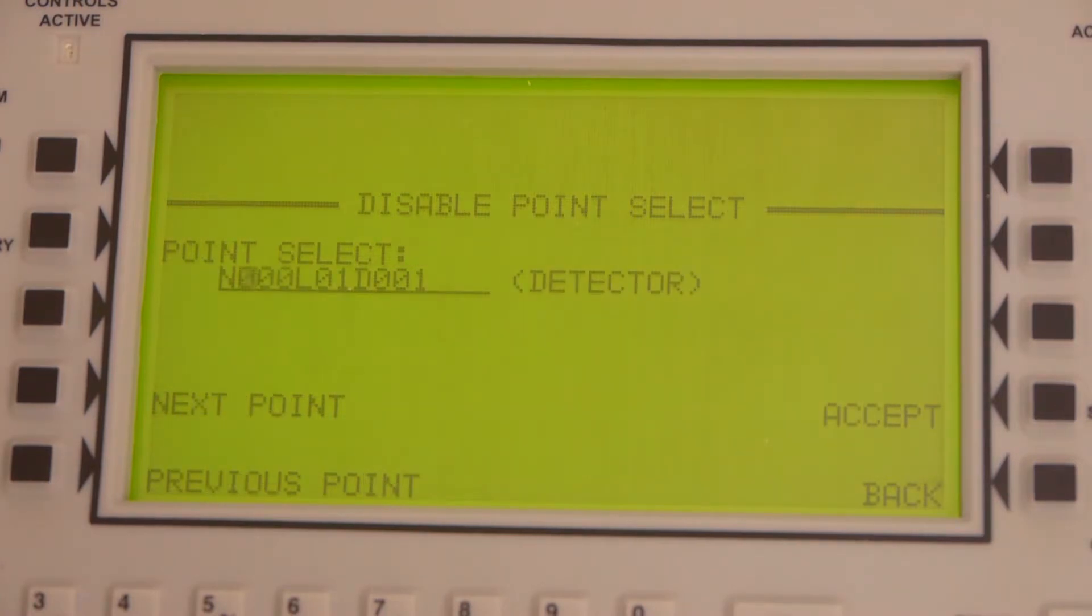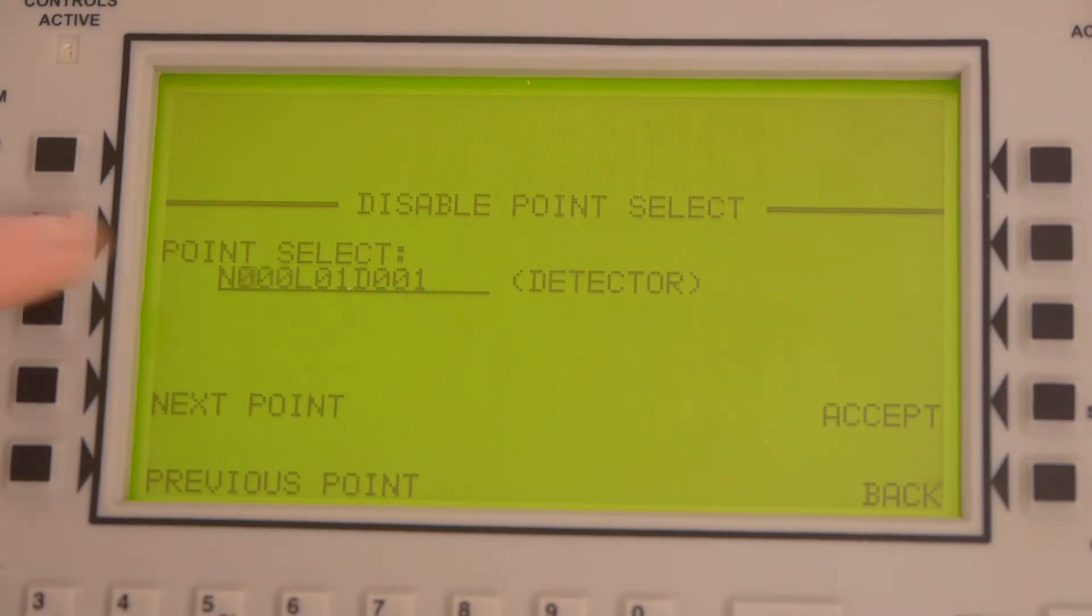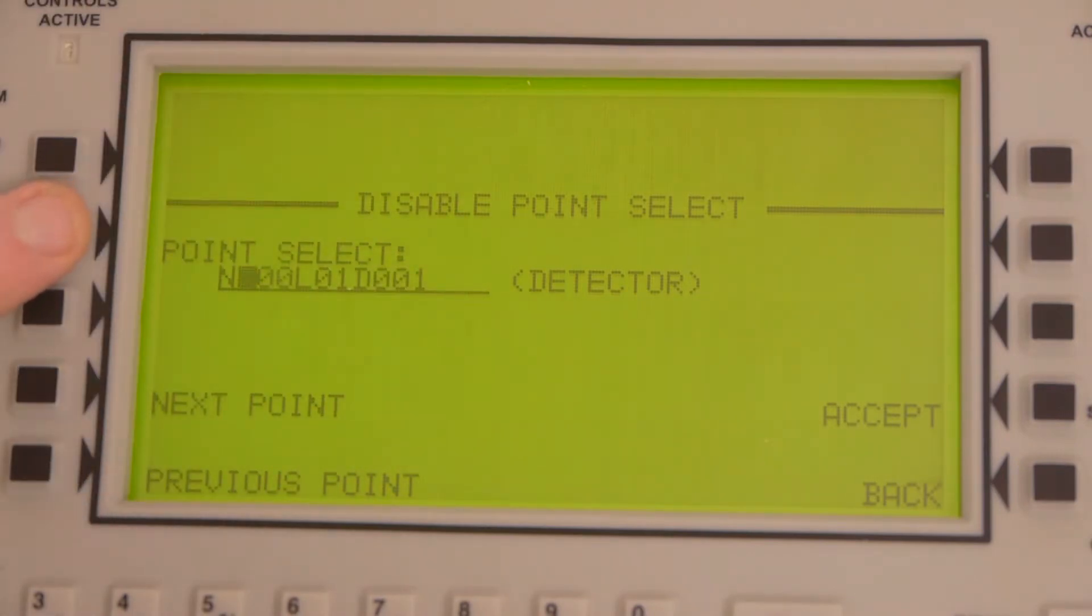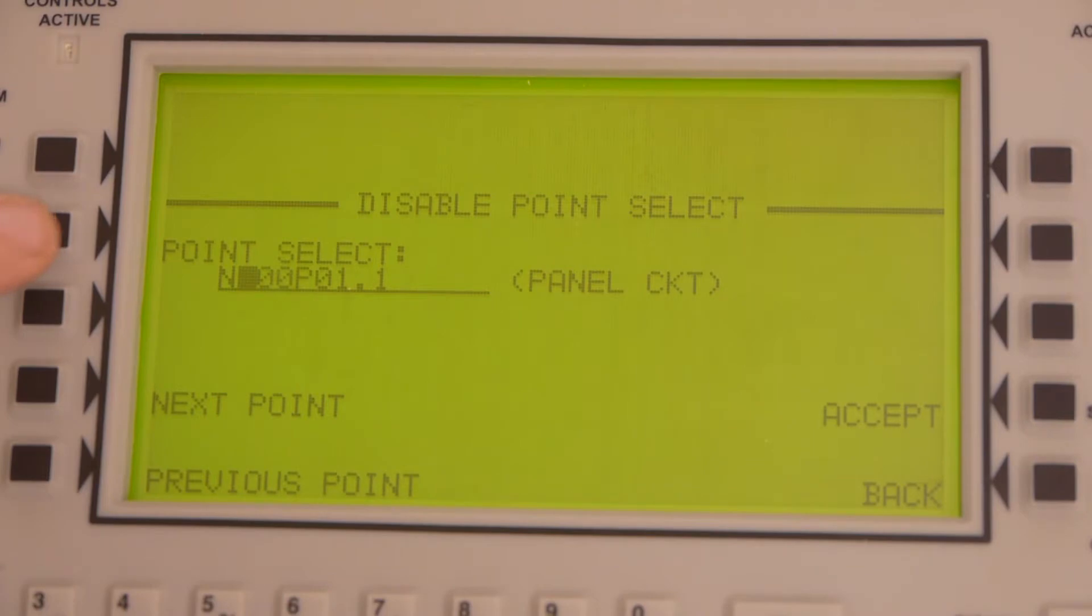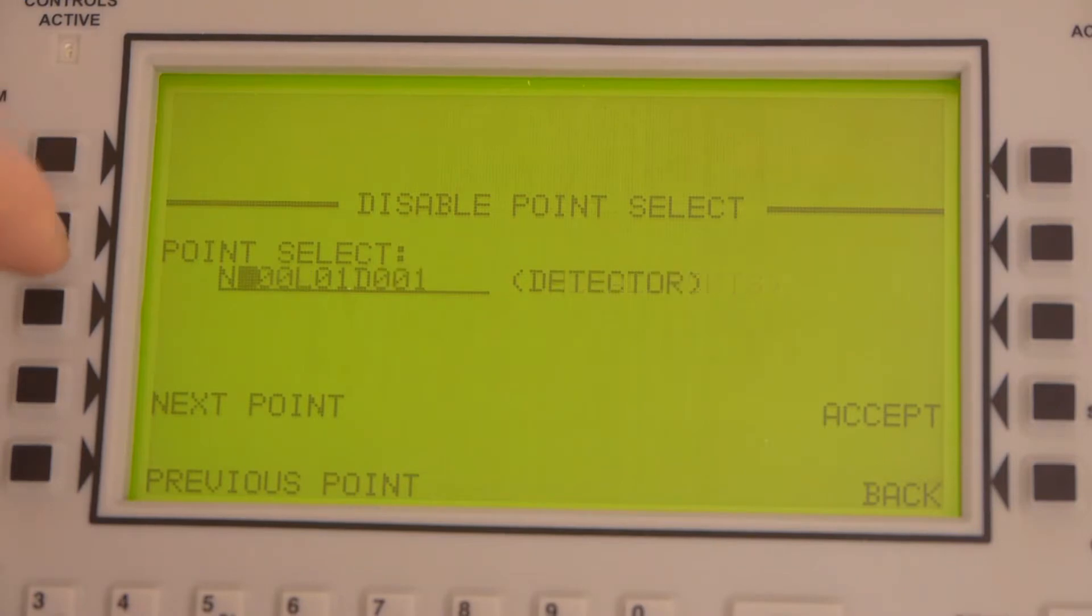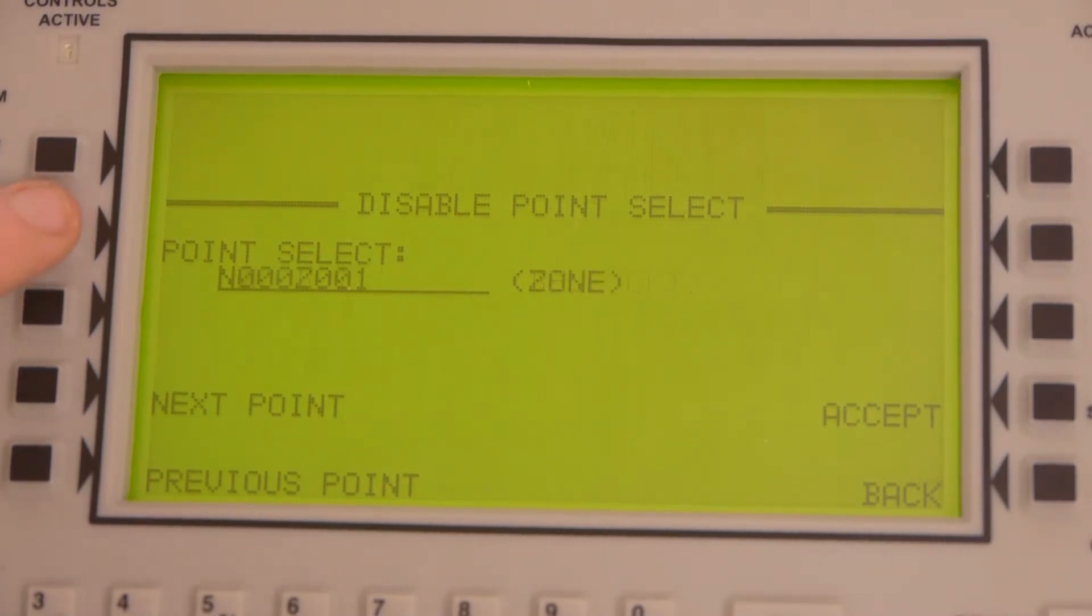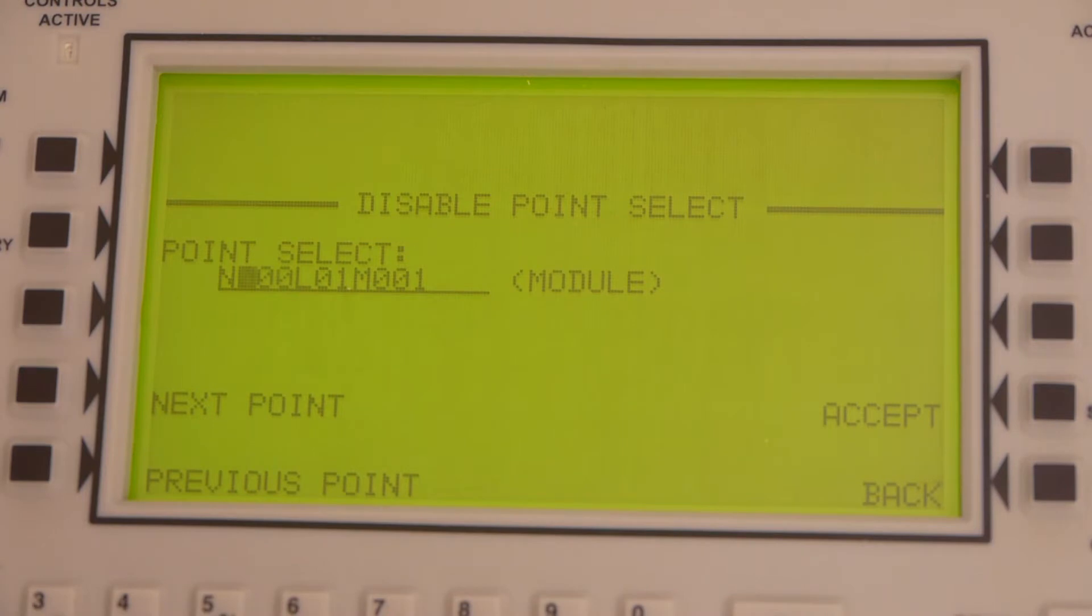This is where we enter in what device it is and where it is. The first thing I have to do is figure out what type of device I'm going to be disabling. Right now it's a detector. But if we're disabling a module, we can press this button once and it's going to scroll down to a module. If it's something else, like a voice circuit, you can scroll through and select the type of device you're trying to disable. There's lots of different options. In this tutorial, I'm just going to be showing disabling a module. There we go, there's a module.